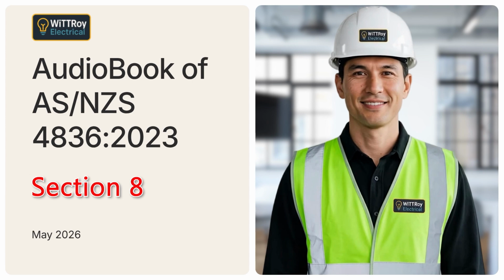Clause 8.5.2. Insulating covers and mats. Clause 8.5.2 explains insulating covers and mats. Insulating mats used with electrical equipment rated below 650 volts must comply with and be tested according to AS/NZS 61111. Insulating covers used with electrical equipment rated below 650 volts must comply with and be tested according to AS 4202. Insulating mats and covers must be visually inspected for defects before and after each use. If they are defective, they must be tagged.